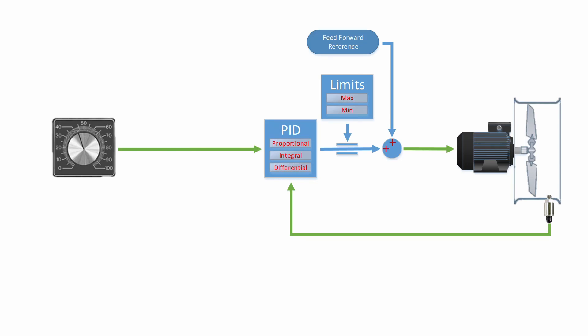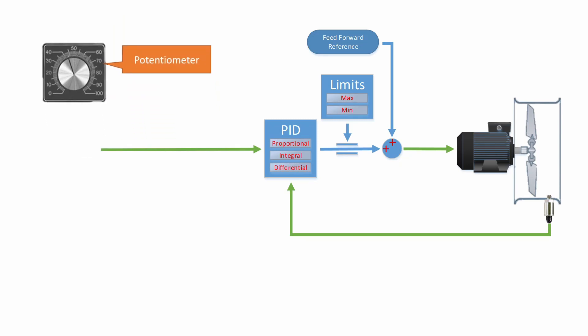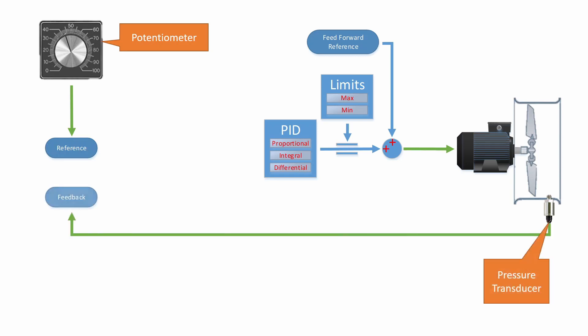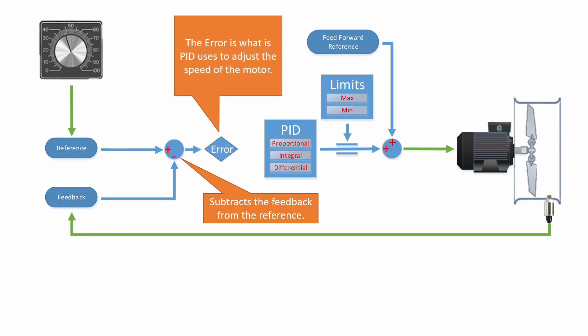Let's see how to set up the input side of the PID loop. The potentiometer is mapped to the reference, and the pressure transducer is mapped to the feedback. The reference and the feedback are subtracted from each other. This produces the error. The error is what the PID uses to trim the speed.